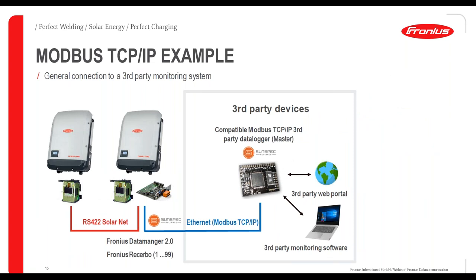The second Modbus variant is Modbus TCP/IP communication, which also enables third-party monitoring. Two inverters communicate with each other via SolarNet using an Ethernet cable, and then connect via Modbus TCP/IP over a standard Ethernet cable to a third-party device — enabling a third-party web portal or monitoring system. Thanks to the SunSpec alliance, this communication standard is implemented in the inverter.